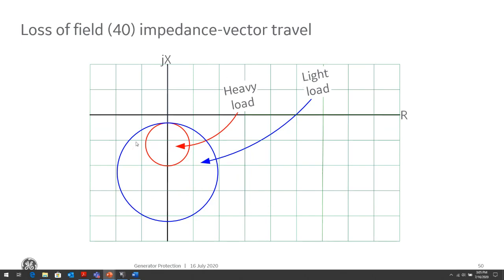So in heavy load conditions, the offset Mho is more stringent in that it will trip fairly quickly. And during light load conditions, we want to have some sort of delay because we do not want to trip the machine for stable power swings, where the locus or the electrical point will start to swing through this curve. And it's likely when it swings, it will swing through this outer region. So we want to be able to coordinate for our worst case power system swing conditions.